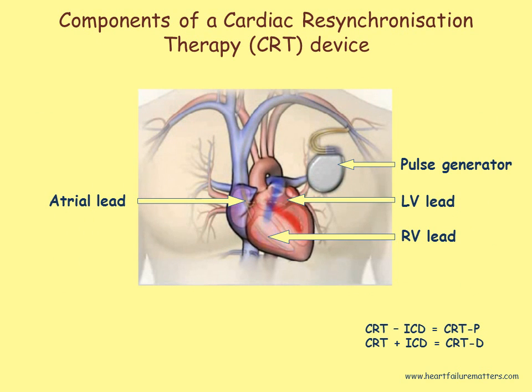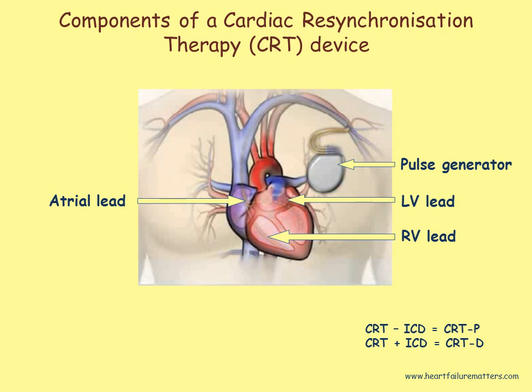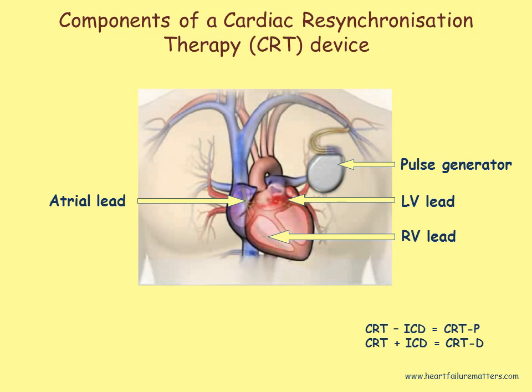The CRT device consists of a pulse generator, or pacemaker, and three leads that are placed into the heart via the left subclavian vein. The first lead is placed in the right ventricle, the second lead is placed in the right atrium, and the third lead is threaded through the coronary sinus and placed posteriorly on the epicardium in a posterolateral coronary vein. A CRT device without an ICD or defibrillator is termed a CRTP. A CRT device incorporating an ICD is termed a CRT-D.